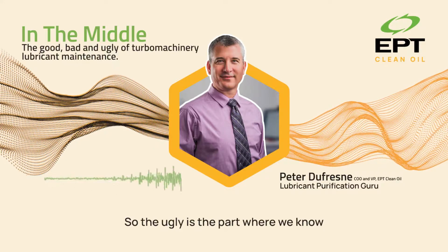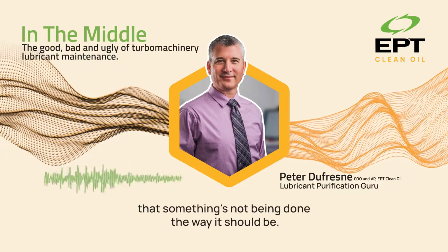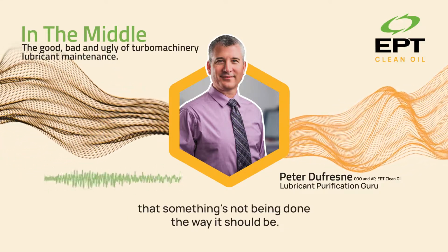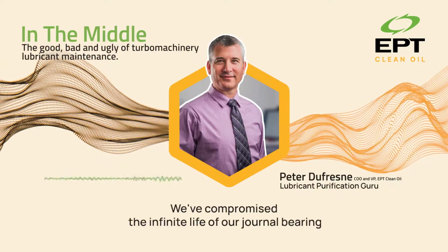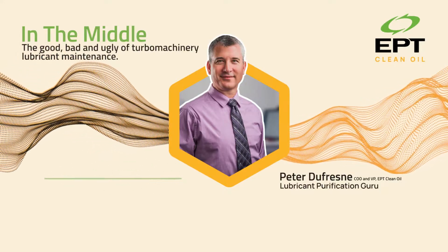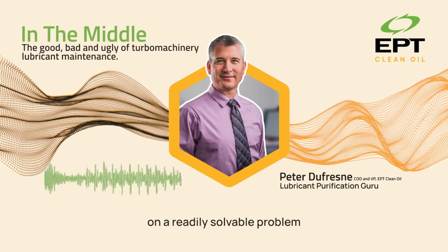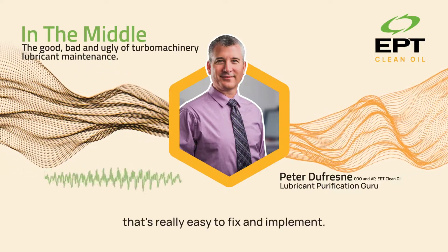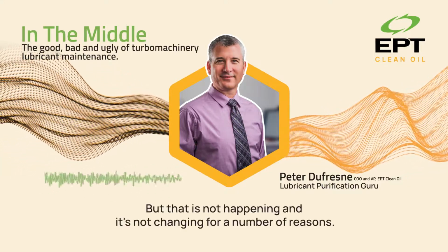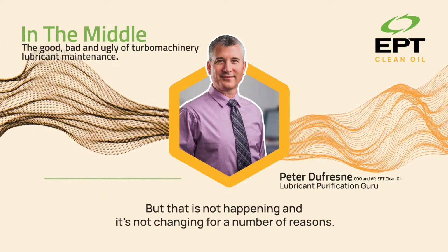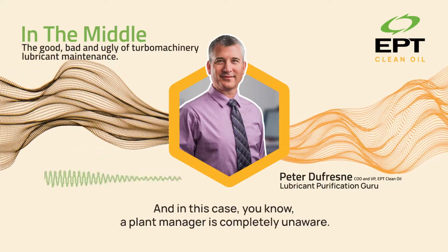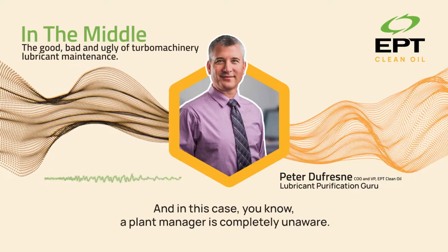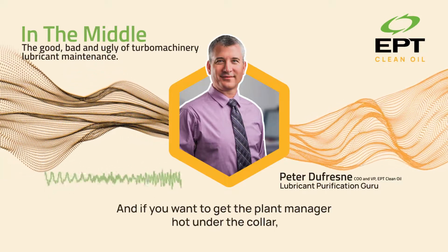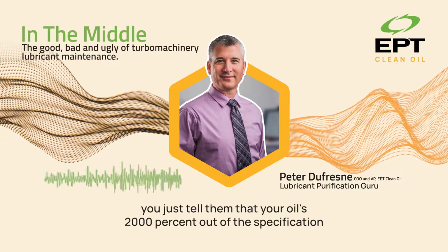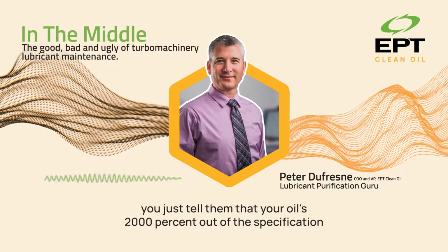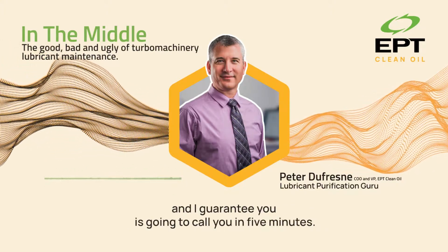So the ugly is the part where we know that something's not being done the way it should be. We've compromised the infinite life of our journal bearing on a readily solvable problem that's really easy to fix and implement, but it's not happening. It's not changing for a number of reasons. And in this case, the plant manager was completely unaware. And if you want to get the plant manager hot under the collar, you just tell him that your oil is 2,000% out of specification, and I guarantee he's going to call you in 5 minutes.